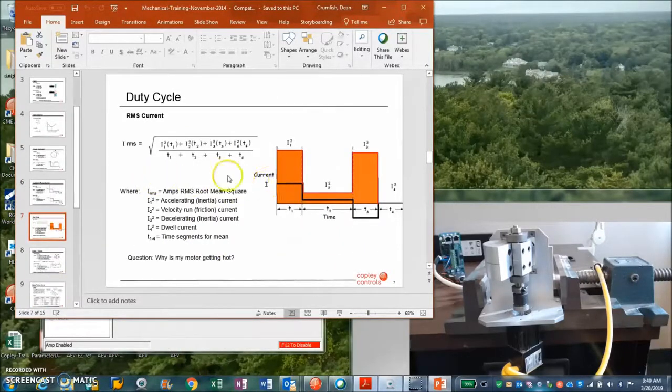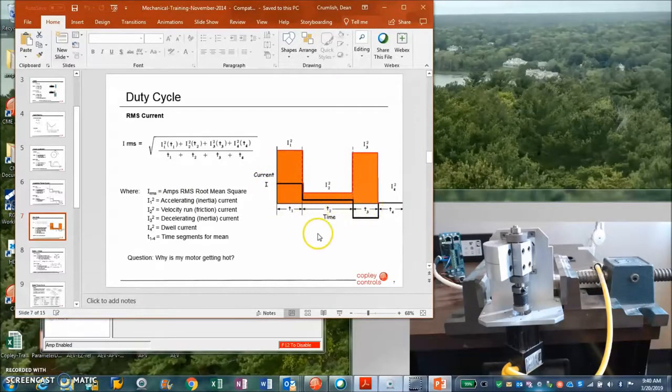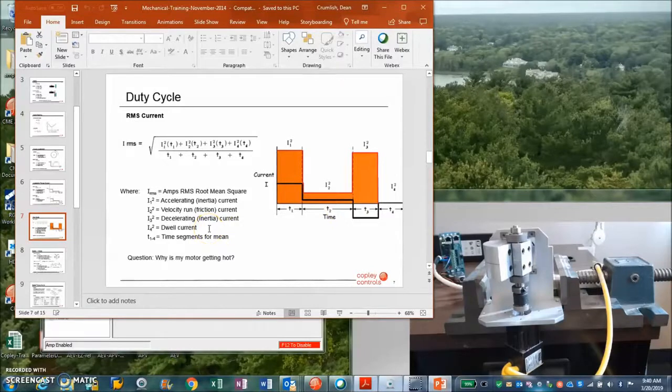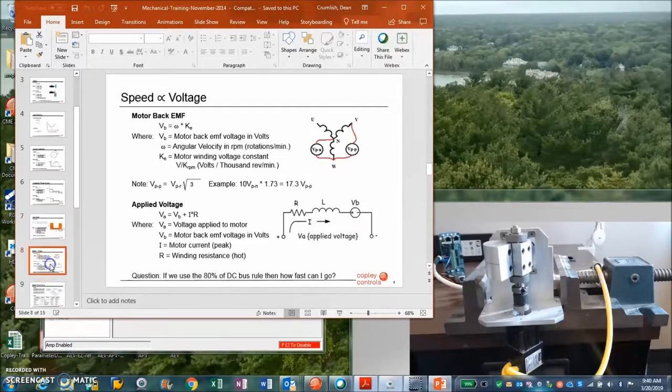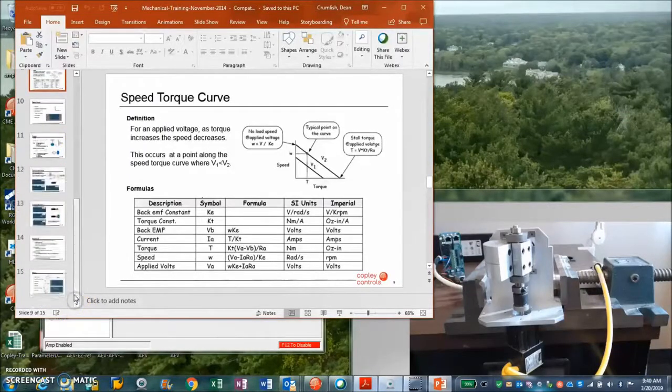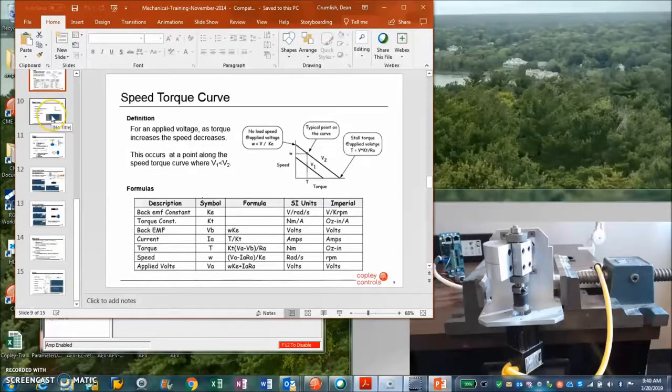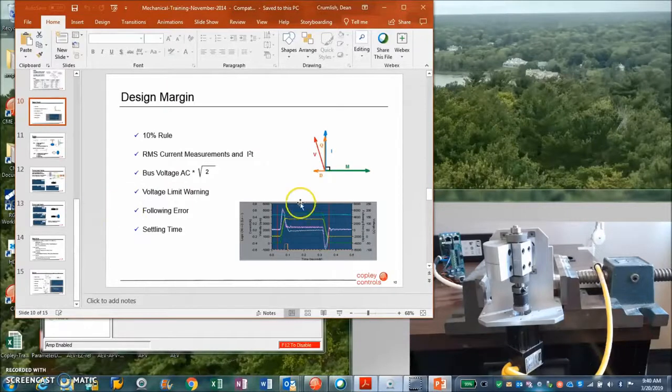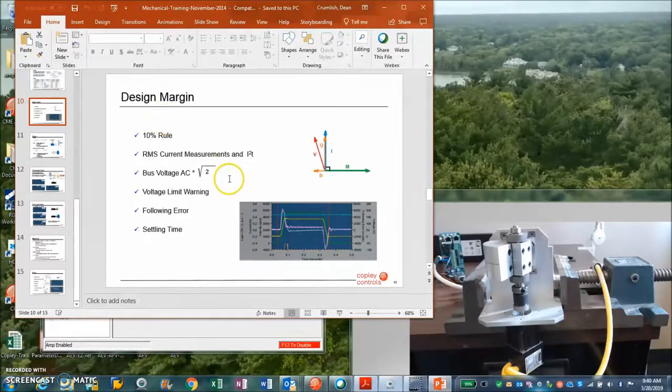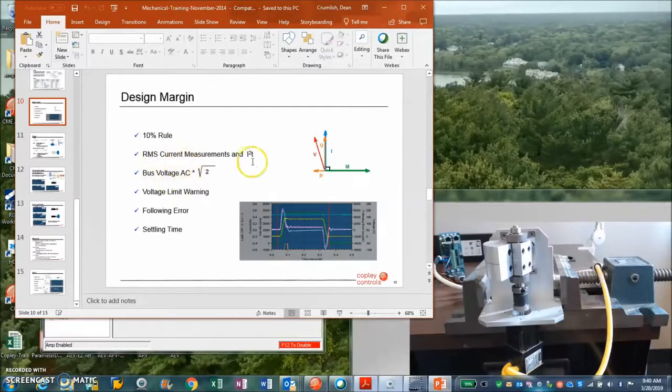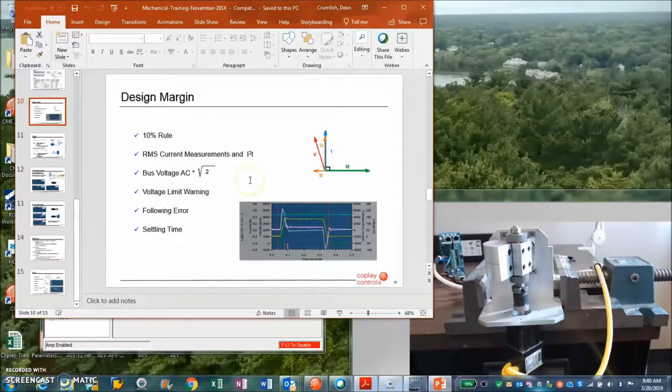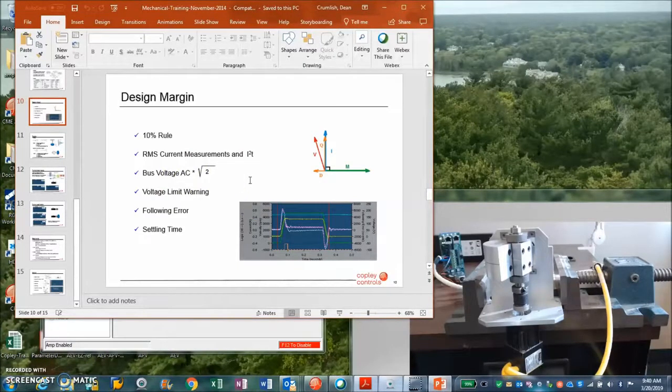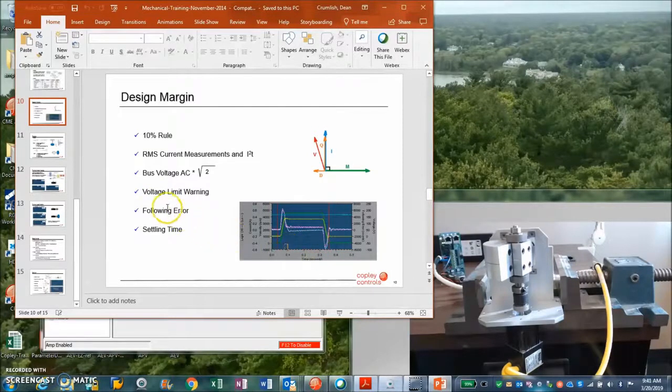Basically, we can see the torque over time is the current over time. The square root of the accelerating, running, and decelerating current—you should make sure this is always less than your continuous current. Voltage gives you speed. There's a bunch of formulas for motor modeling. Just sort of a design rule: give yourself some margin. Make sure your RMS current over time is less than the motor's. Make sure you've got some DC bus—use up 80% if you want, but leave yourself some headroom.